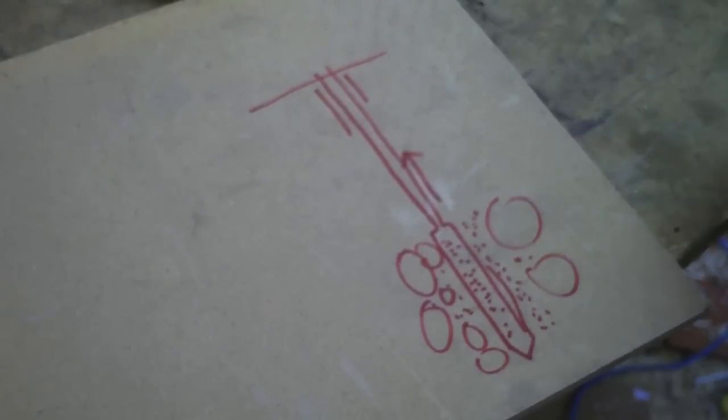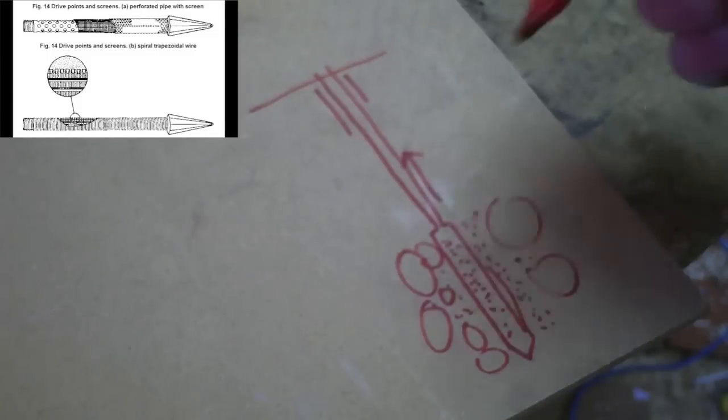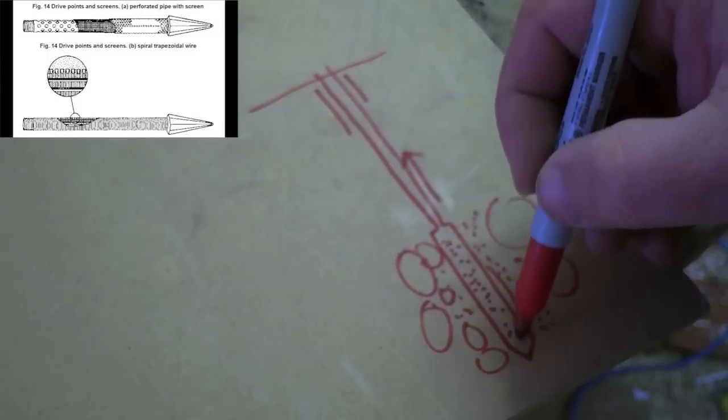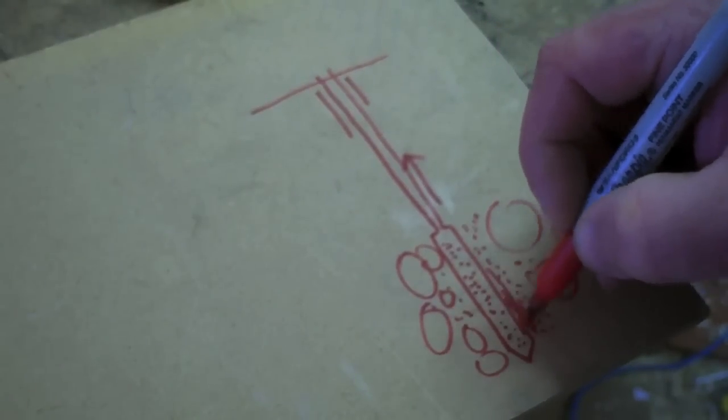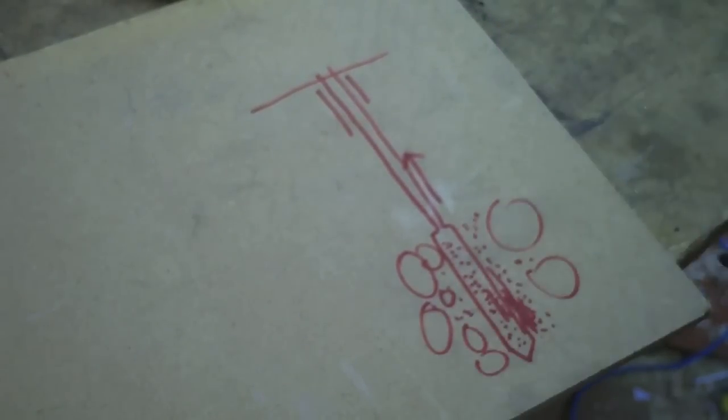But on reflection, that sand point should be filtering all those sand particles. It shouldn't be big stuff coming out, not like beach sand. The screens on the sand point are finer than that. It makes me wonder if maybe a big rock or something was hit and part of the screen on the sand point might have been damaged.